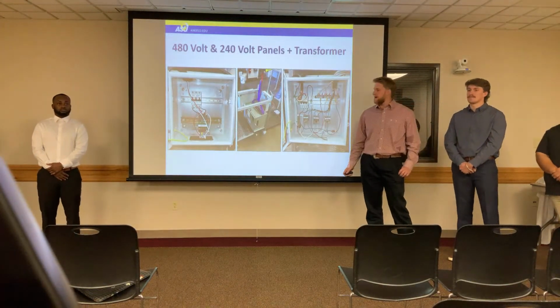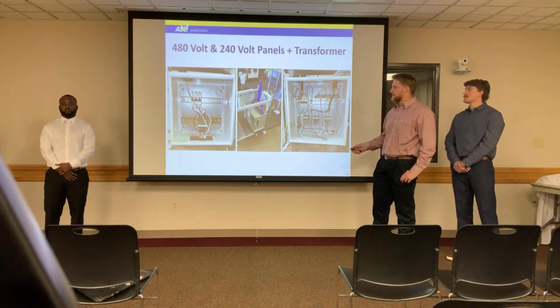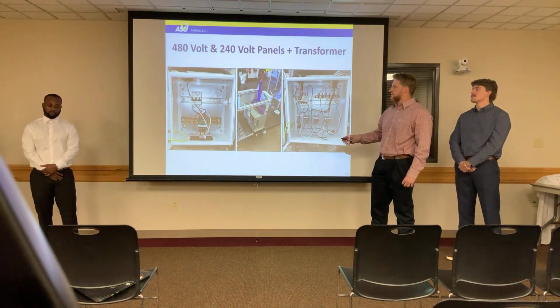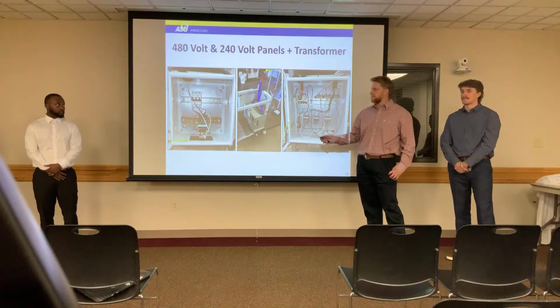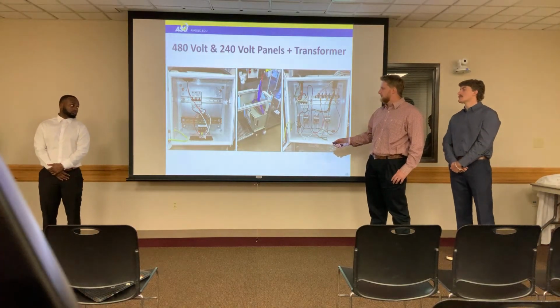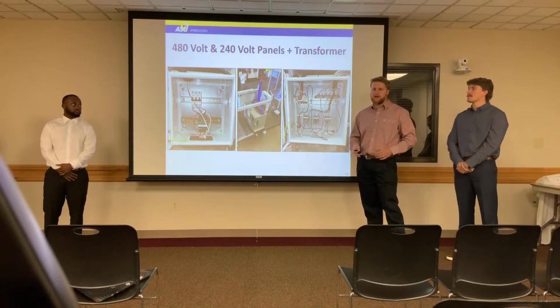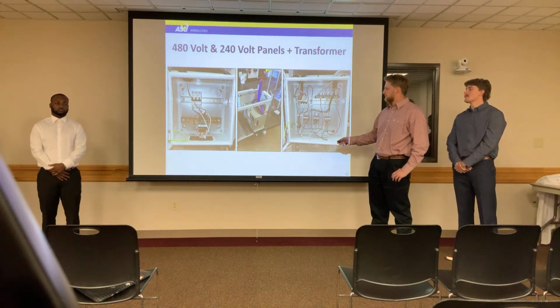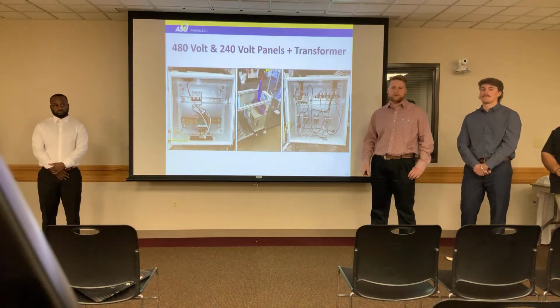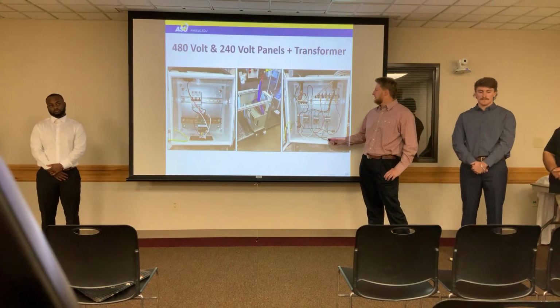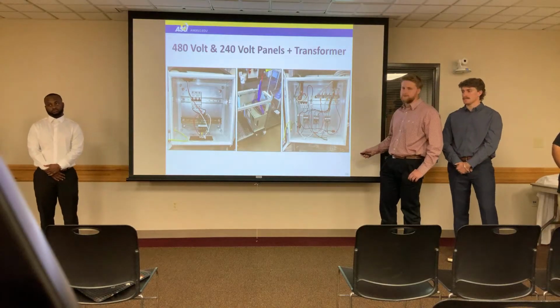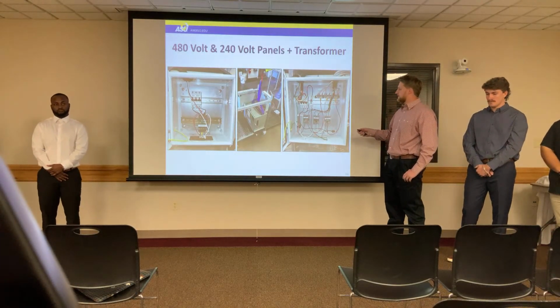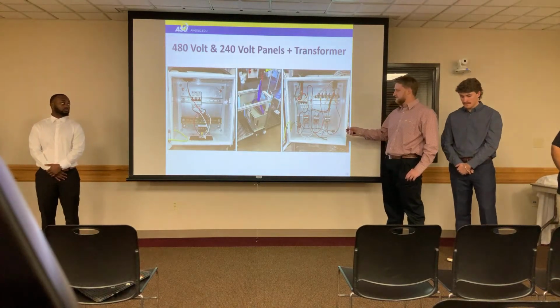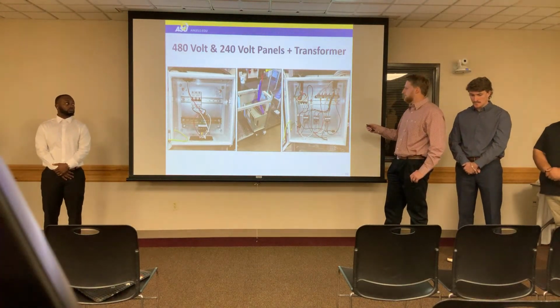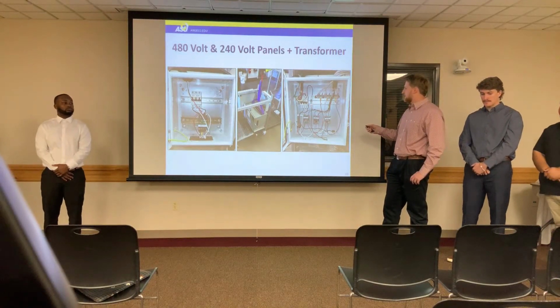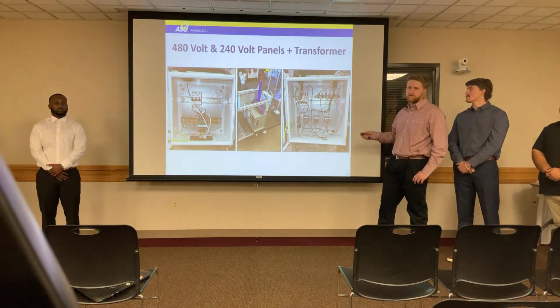So these are some pictures of our panels. On the far left, we have our 480 volt panel. So power will be wired in through this breaker right here, the 480 volts, which will run into the contactor, which shuts off power if needed. So from there, it goes into the transformer where it is stepped down to 240 volts of alternating current, and then we'll run into our 240 volt panel. So it'll run into the breaker here, which then powers all three of these solid state relays, which run into our heater bus bar here. So this takes 3 lines of power in order to power all 4 of our heaters.